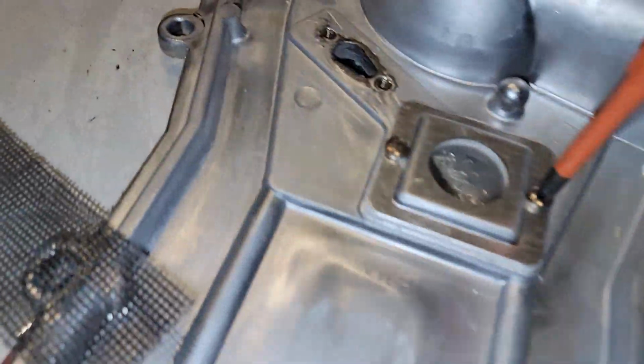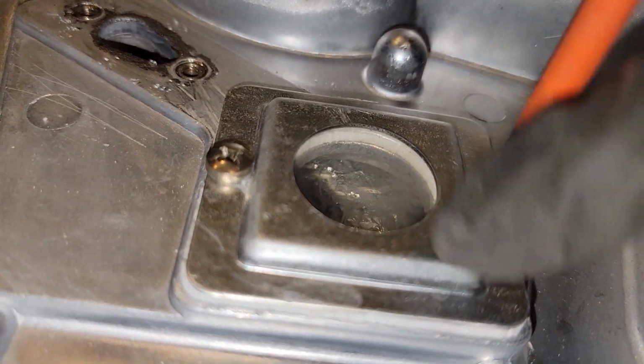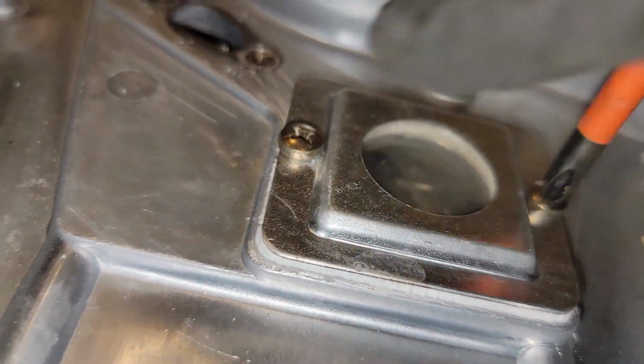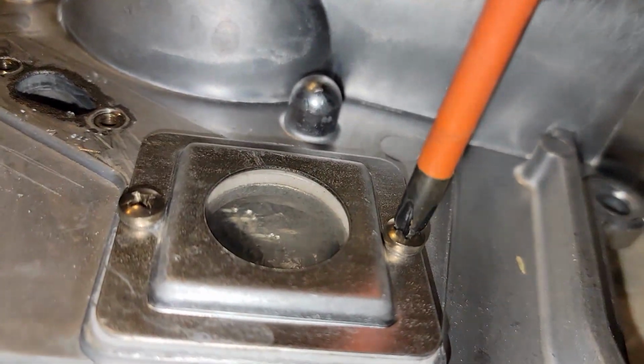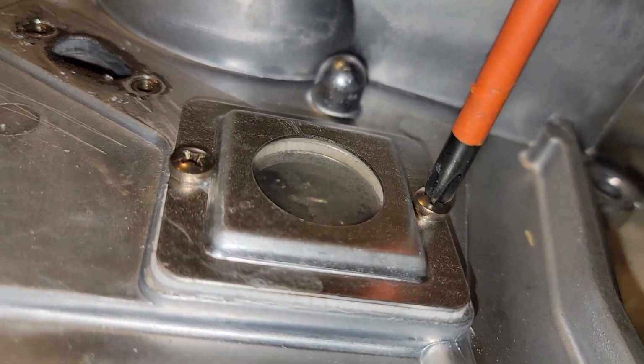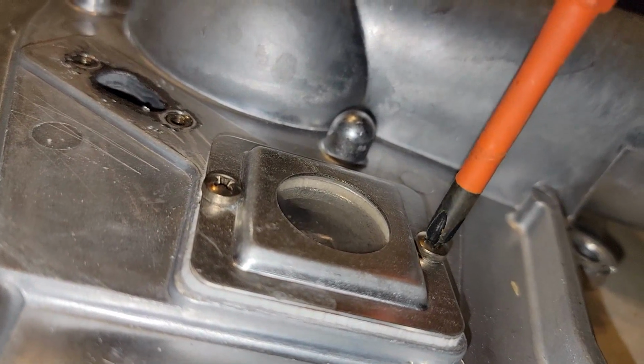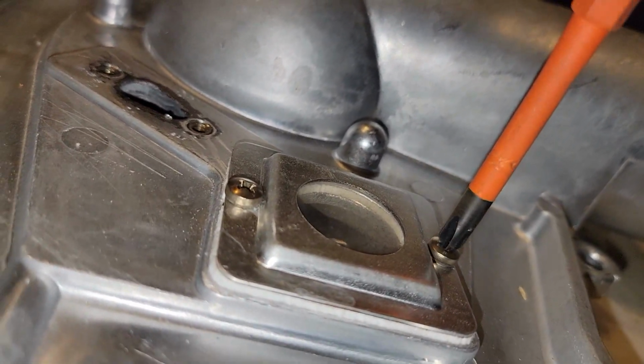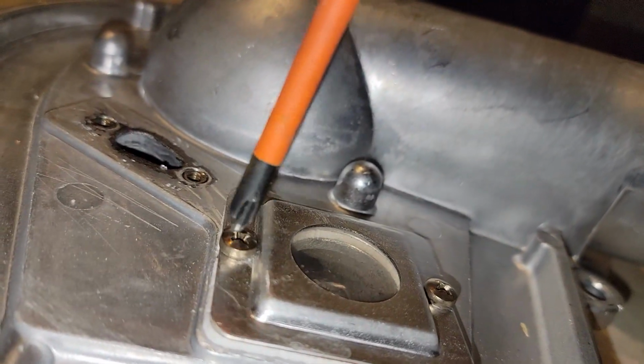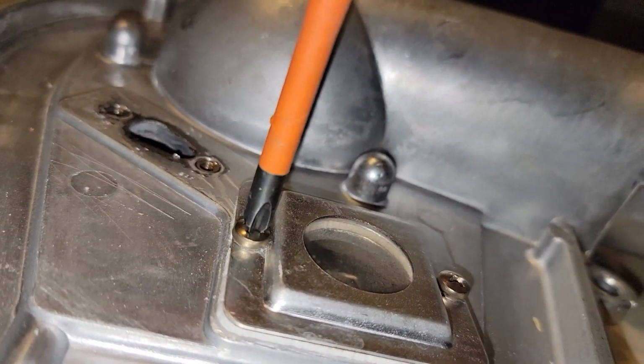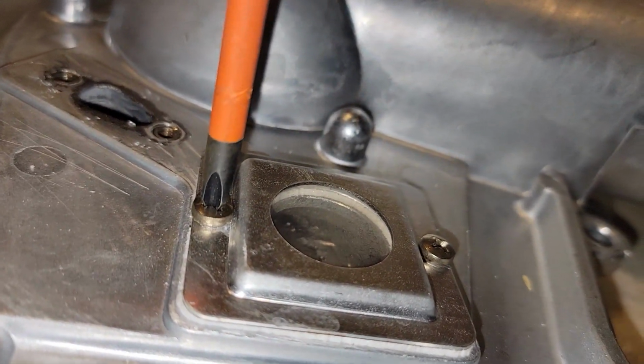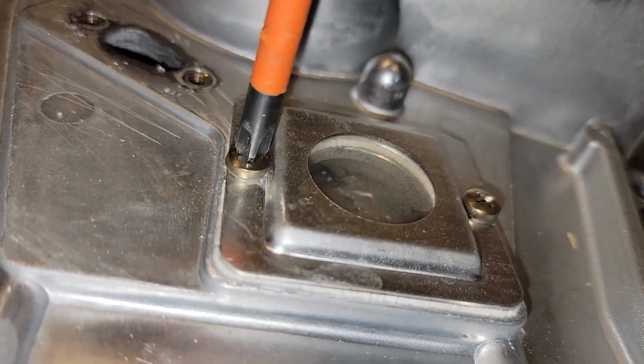One thing about replacing this gasket is you're tightening this metal piece down onto this piece of glass. So you have to be careful because it does need to be tight in order to create the seal, but you also don't want to crack the glass. And as you tighten it, you can kind of hear the glass moving in there.